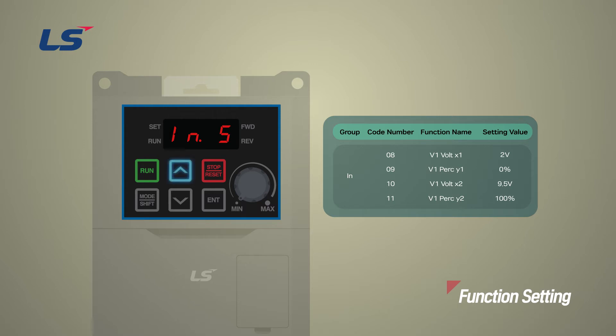Set the minimum input voltage to 2 volts in ingroup 8, and set the corresponding input level to 0% in ingroup 9. Set the maximum input voltage to 9.5 volts in ingroup 10, and set the corresponding input level to 100% in ingroup 11.